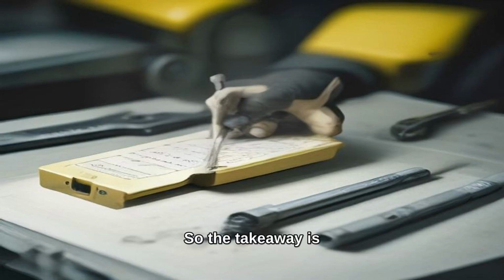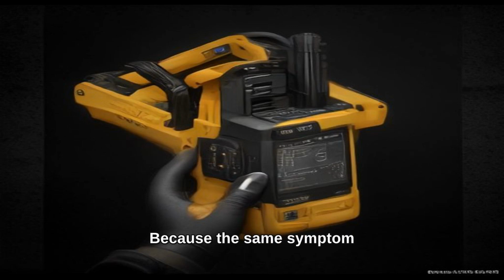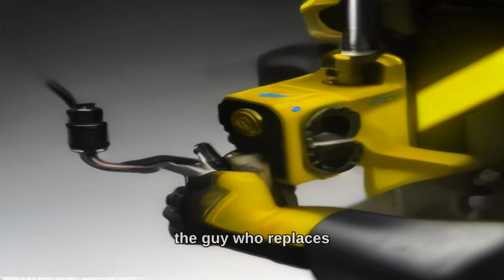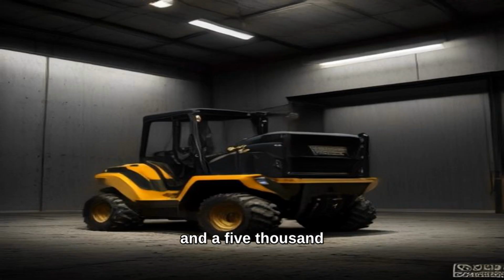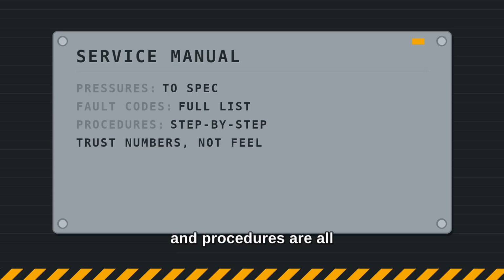So, the takeaway is simple. When a code shows, write down those numbers and look them up before you touch a wrench. Because the same symptom can be a filter or a pump, and only the code tells you which one it is. That's the difference between the guy who replaces a coil and the guy who replaces a whole controller. Read the whisper, and a 5600 will tell you its own weak points before they ever become your weekend. The exact pressures, codes, and procedures are all in the service manual linked below. Trust the numbers, not the feel.